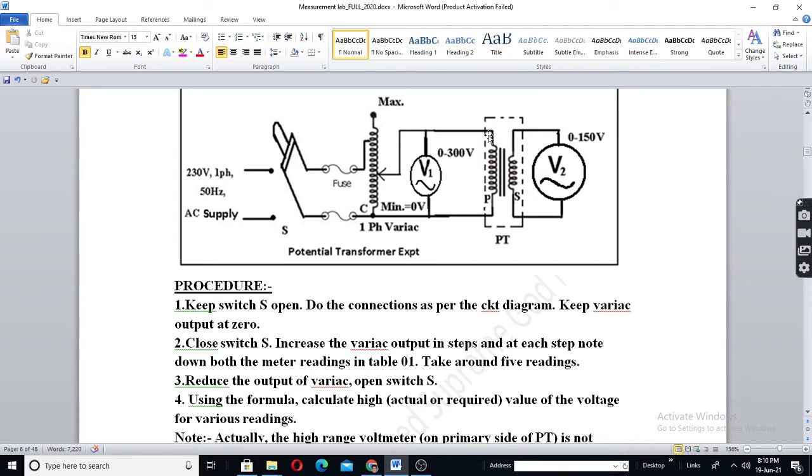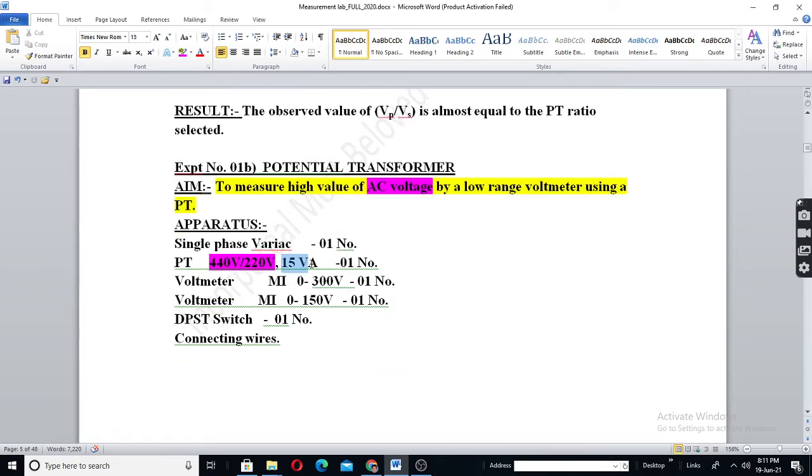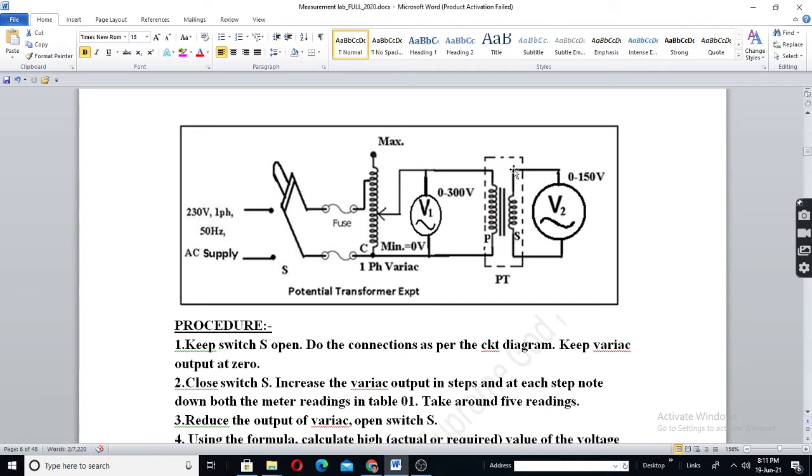See, PT is a normal potential transformer, a normal transformer. But it cannot deliver load. You cannot connect load in the secondary. Hence, its VA will be less. You can see here, only 15 VA. So, the current in the wires or the coils will be very much less. Practically, theoretically it should be zero. But practically there will be magnetizing current. Hence, there will be some current.